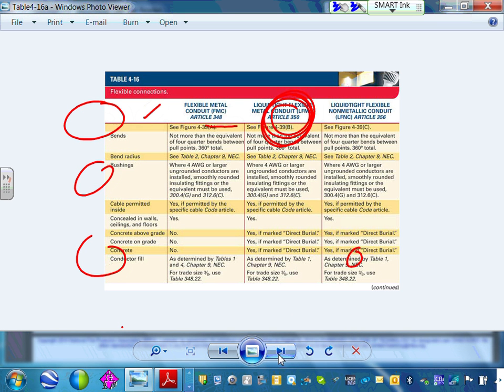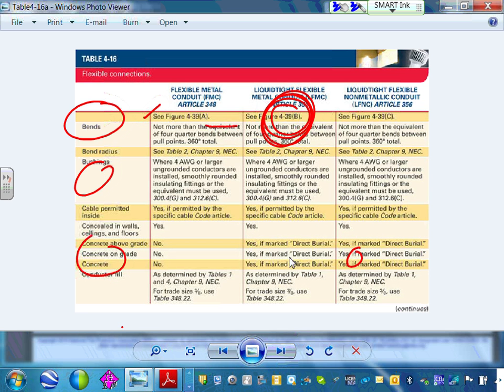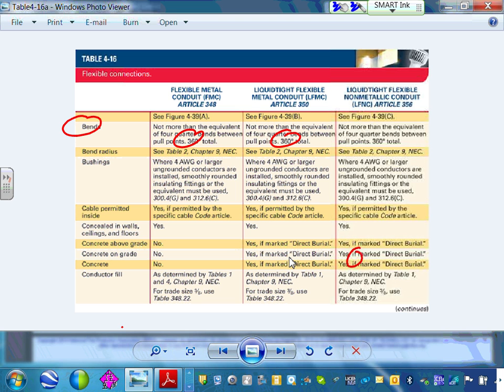Let's go compare between these. That's in table number, flexible metallic conduit, starting at page 141, table 4.16. Let's look at these. Very quickly, again, this is only tied to equipment, remember, even though it's wiring methods. Tied to equipment. Now guess how many bends you can put on these.